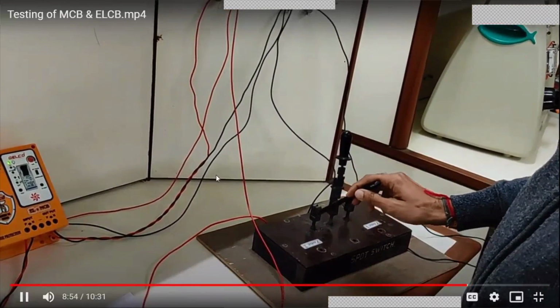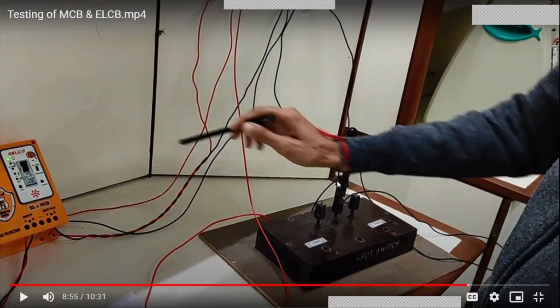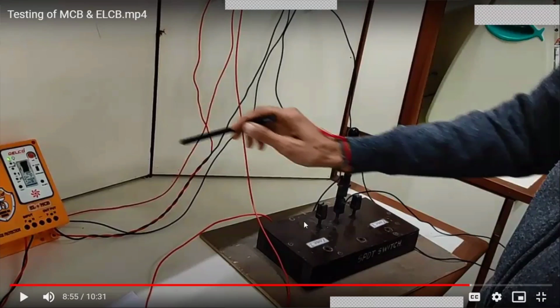Now we will connect this SPDT switch first, dragging it to earth, and close the switch to connect earth to phase. In that case the ELCB will trip and cut the supply from the load, so in the ammeter you will see close to 0 ampere current, not exactly 0 but around 0.01 ampere, since there is also some error in the measuring instruments.